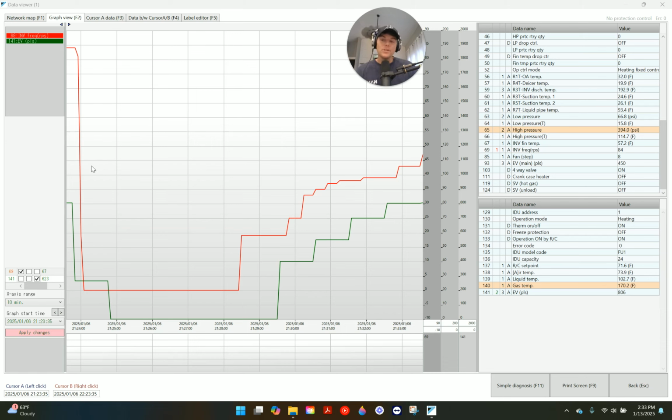But what I'm going to do is determine what determines head pressure, right? If it's going to my indoor heat exchanger because I'm in heat, what's determining my head pressure is probably my valve pulses, and how much back pressure it's going to build up on that expansion valve. Is it opening wide open? Is it going all the way closed? This is important information that I need to know.